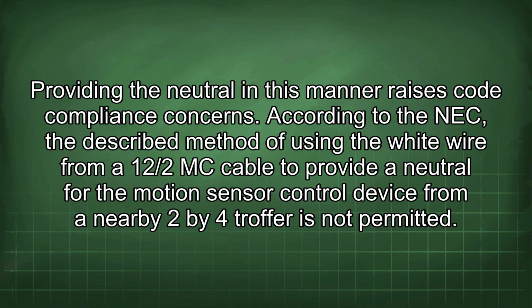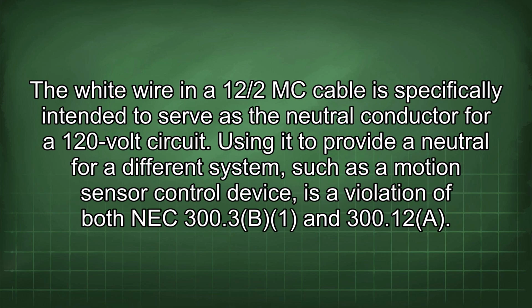According to the NEC, the described method of using the white wire from a 12/2 MC cable to provide a neutral for the motion sensor control device from a nearby 2x4 troffer is not permitted. The white wire in a 12/2 MC cable is specifically intended to serve as the neutral conductor for a 120-volt circuit. Using it to provide a neutral for a different system, such as a motion sensor control device, is a violation of both NEC 300.3(B) and 300.12(A).